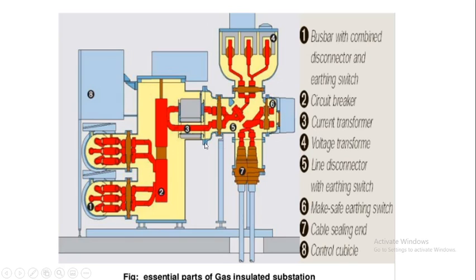Then third is a current transformer. So this is a current transformer that you can see. I'll take a pen over here. So this is a current transformer, CT. And the fourth one we have is a voltage transformer. Here we have the complete voltage transformer. And the fifth one is a line disconnector with the earthing switch. As I have already mentioned, these earthing switches are nothing but providing a low impedance path. Then the sixth one is a make safe earthing switch. This is the make safe earthing switch component.